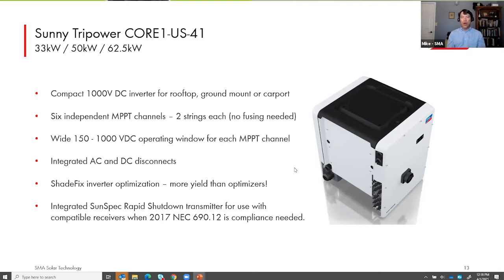On the Core 1 line, you can see the handle for the DC disconnect on the side facing the screen, and on the opposite side there's a built-in AC disconnect as well. The input structure has 12 string inputs on each Core 1, broken up as 2 string inputs onto 6 independent tracking channels. Each tracking channel is handled independently by the inverter, so it's essentially like getting 6 inverters in each box. The maximum of 2 strings per input channel also means no series input fusing is needed, so there's no combiner box required, no worries about fusing, and nothing extra to stock for spares for O&M. Again, we're trying to incorporate all required balance of system components into the box.